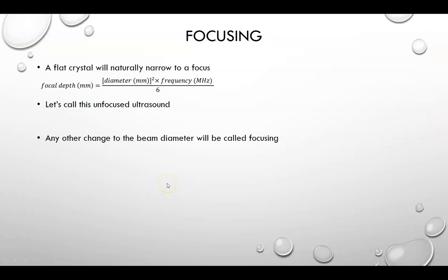Let's talk about focusing. Everything discussed so far about beam shapes has been about a flat crystal. An unfocused crystal has a natural focal length. A flat crystal naturally focuses at a focal depth equal to the diameter of the crystal squared, times the frequency, divided by six. We generally call this unfocused ultrasound.